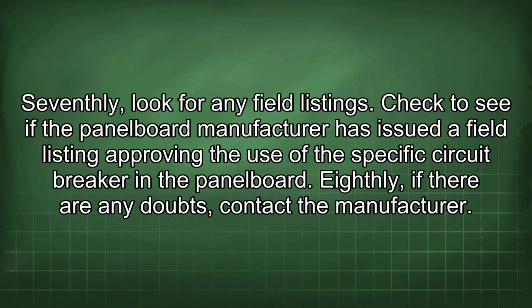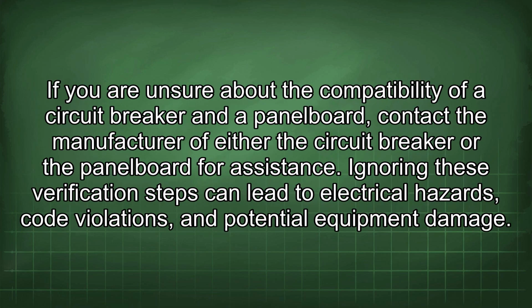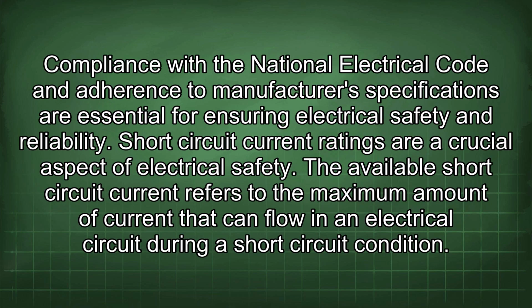Check to see if the panelboard manufacturer has issued a field listing approving the use of the specific circuit breaker in the panelboard. Eighthly, if there are any doubts, contact the manufacturer. If you are unsure about the compatibility of a circuit breaker and a panelboard, contact the manufacturer of either the circuit breaker or the panelboard for assistance. Ignoring these verification steps can lead to electrical hazards, code violations, and potential equipment damage. Compliance with the National Electrical Code and adherence to manufacturer specifications are essential for ensuring electrical safety and reliability.